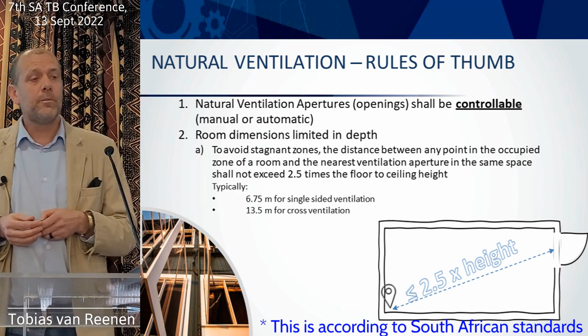So the natural ventilation apertures or openings must be controllable, and that's largely to do with the psychology of naturally ventilated spaces. People, if they can't control a ventilation opening, they will block it permanently. If they can control it, when conditions aren't favorable, they'll close it, but at least you'll still be able to open it when you need it at some time. So please make sure that your natural ventilation openings are controllable to some measure. Otherwise, people are going to override those measures and you end up with no ventilation.